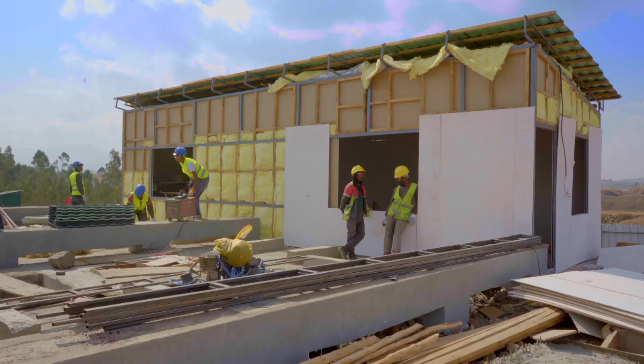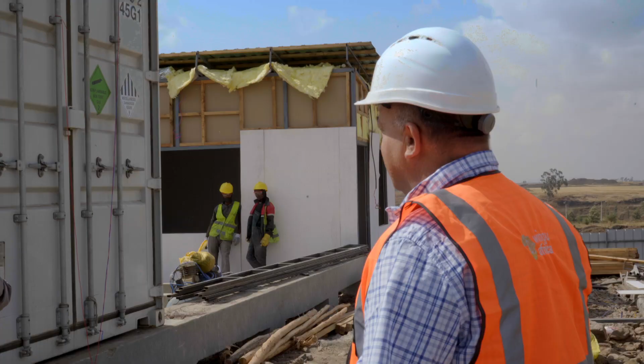On my right hand side we've got our power modules. In all cases across the full facility we have a true A and B parallel redundant system, so we have the luxury of losing a complete leg without losing customer service. We have power module B and power module A, which is effectively the energy, the heart and soul of the data center, housing the UPSs and batteries to keep the power going in the event of a mains failure.